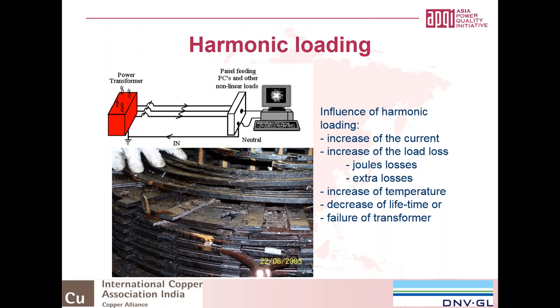We did an investigation on this transformer because it failed. It's obvious that this transformer has failed and could not be used within that industry. And then we found out that this transformer had a heavy harmonic loading profile, meaning that due to the harmonics it got more losses in specific places.